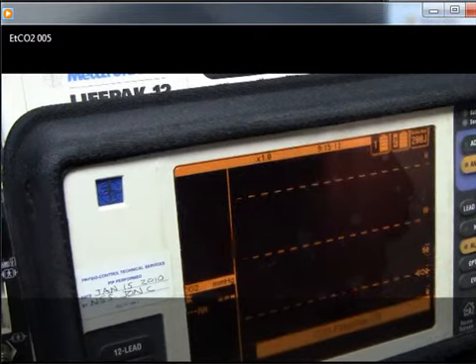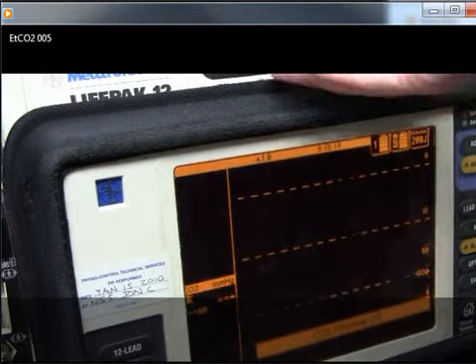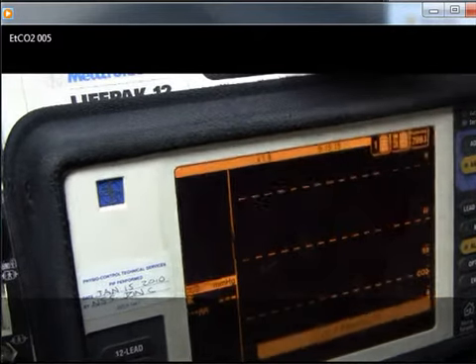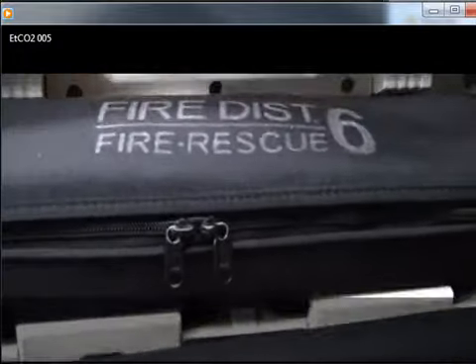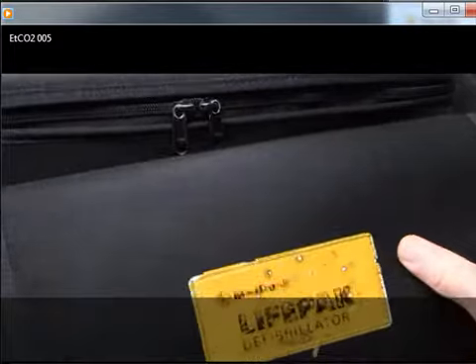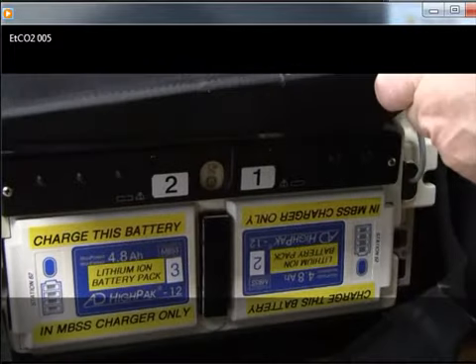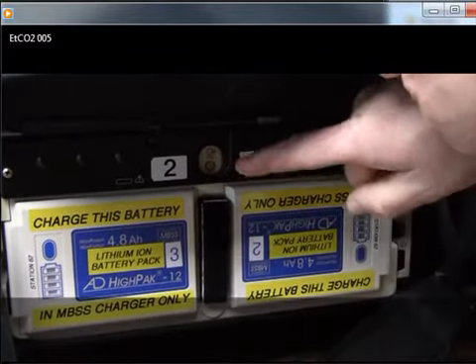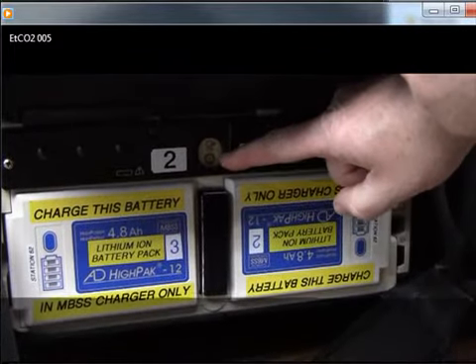If end-tidal CO2 values are consistently lower than expected, check the end-tidal CO2 exhaust port located behind the monitor. This could be blocked, fouled, or obstructed.